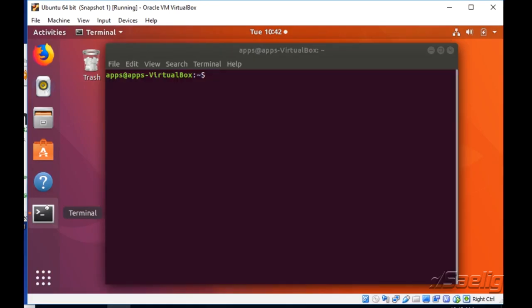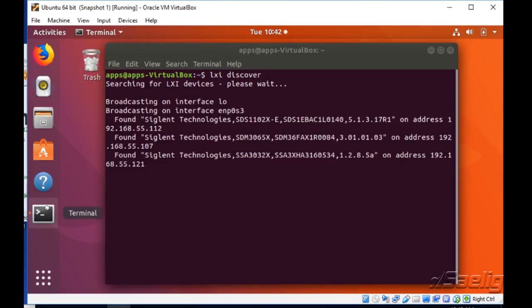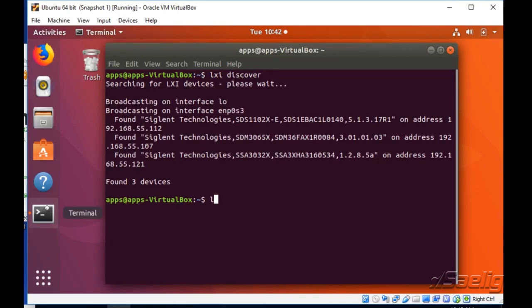We're just going to fire up a terminal. I've already loaded the LXI Tools. The really cool thing about LXI Discover is it's going to go out and look at all of the devices that are attached to the LAN. You can see all three of them have returned their IDNs or their identification strings.